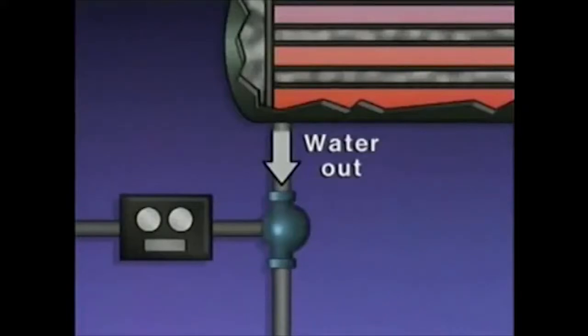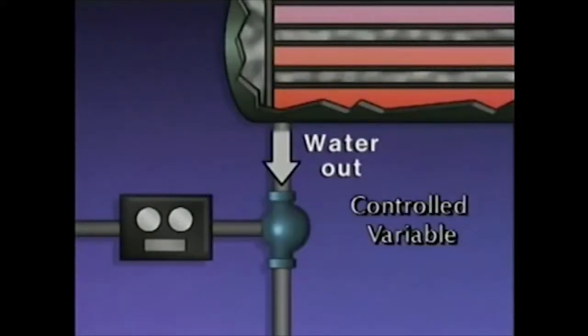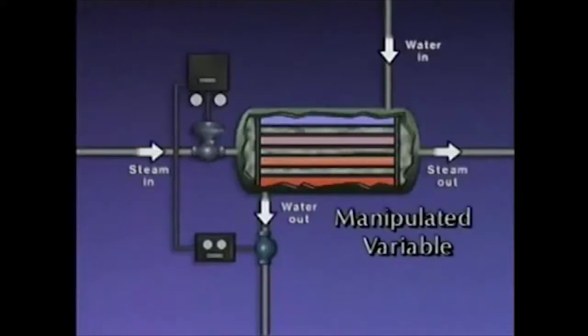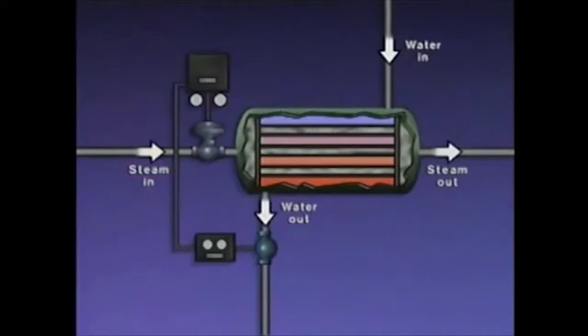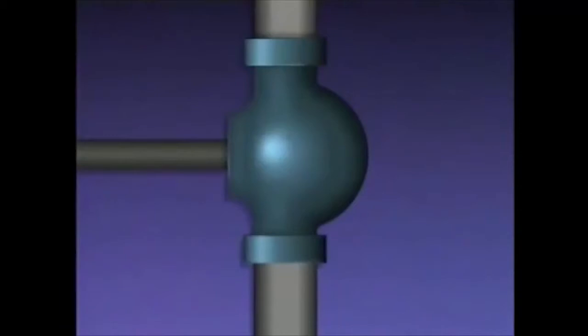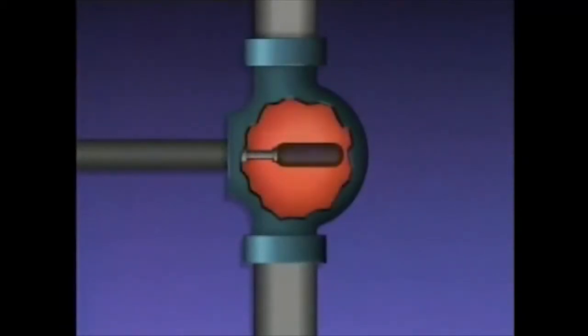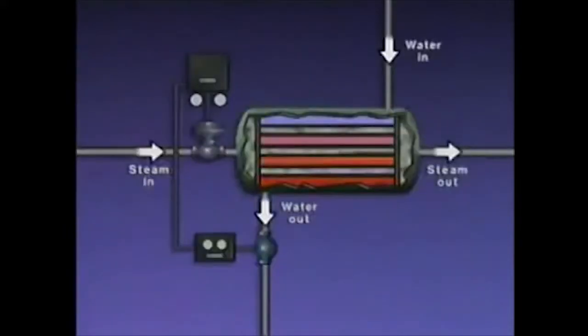The control variable in this system is the water temperature at the outlet. The outlet water temperature is used to determine whether a control action is needed to maintain the outlet temperature. So, it is the measured variable in the system. If the water temperature at the inlet stream changes, the temperature sensor detects the change in temperature and changes the signal it sends to the transmitter.